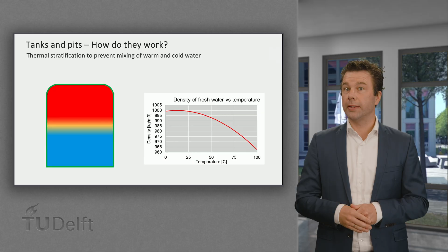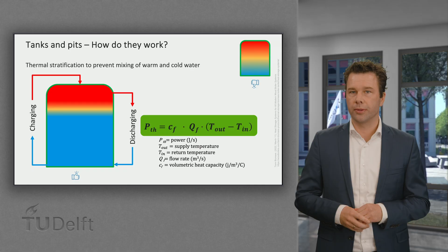It is important because, like all sensible heat storage technologies, the amount of thermal power output is defined by the flow rate and the volumetric heat capacity of the storage medium, together with the temperature difference between the supply and the return temperature. Maintaining this stratification is key for ensuring high heating power availability during discharging.